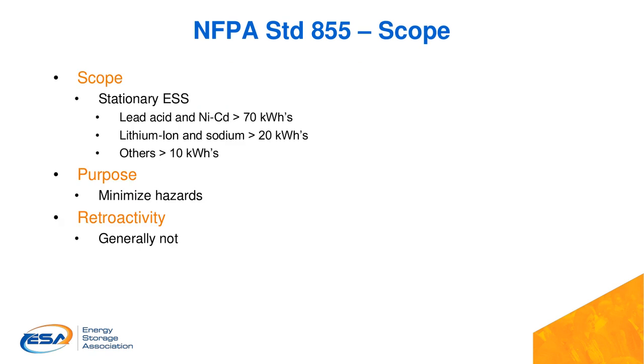So what's the scope of Standard 855? Ostensibly, it's stationary energy storage systems larger than 70 kilowatt hours for lead acid and NiCad, and 20 kilowatt hours for lithium-ion, sodium, and 10 for others. The purpose is to minimize hazards—I've lifted that language straight from the standard.